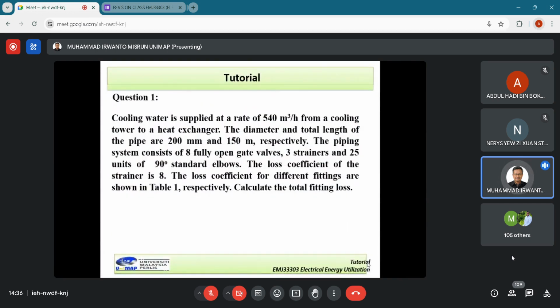Okay, we can see the first question. The question is, cooling water is supplied at a rate of 540 meter cubic per hour from a cooling tower to a heat exchanger. This exchanger we can also call a condenser. The diameter and total length of the pipes are 200 millimeters and 150 meters respectively. The piping system consists of 8 fully open gate valves, 3 strainers, and 25 units of 90 degree standard elbows.